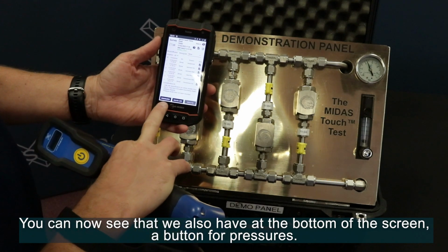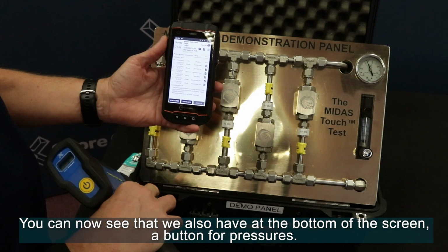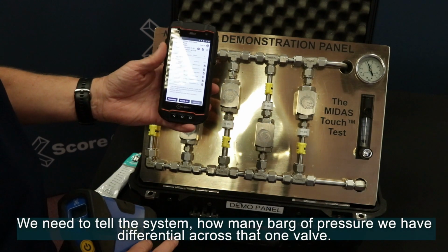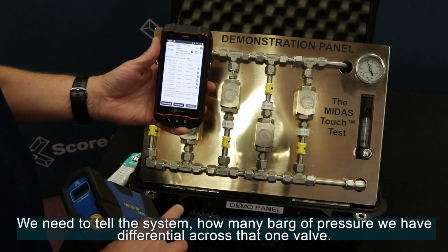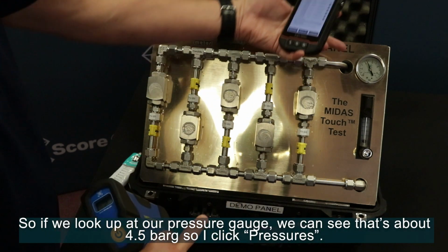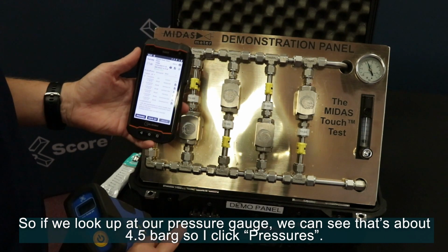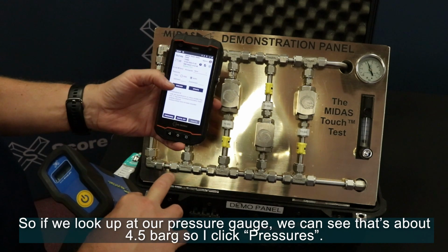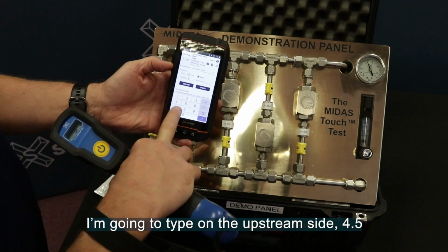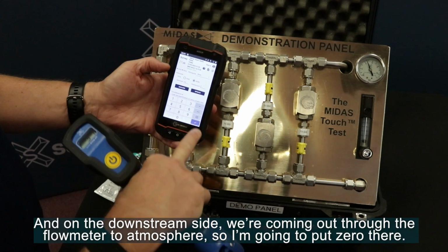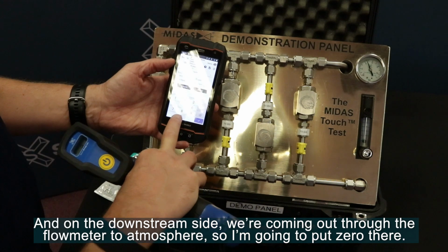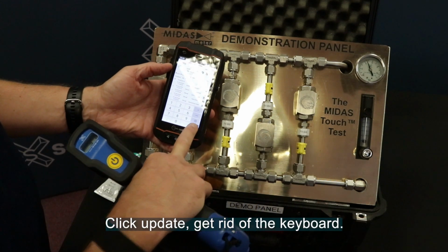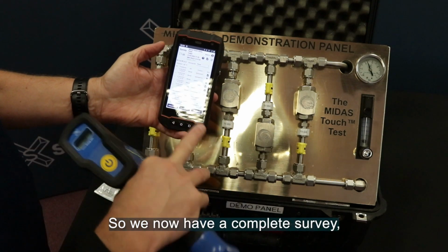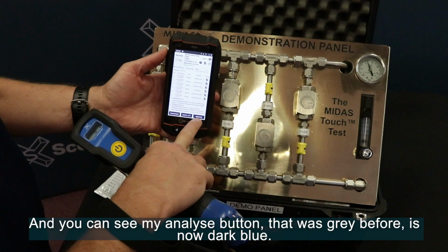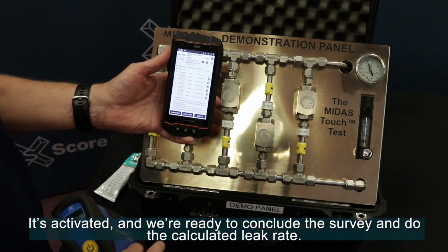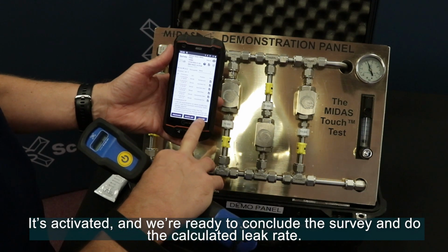You can now see that we also have at the bottom of the screen a button for pressures. We need to tell the system how many bars of pressure we have differential across that one valve. So if we look up at our pressure gauge, you can see that's about 4.5 bar. So I click pressures. I'm going to type in on the upstream side 4.5, and on the downstream side we're coming out through the flow meter to atmosphere, so I'm going to put 0 there. Click update, get rid of the keyboard. So we now have a complete survey, and you can see that my analyze button, which was grey before, is now dark blue. It's activated, and we're ready to conclude the survey and do the calculated leak rate.